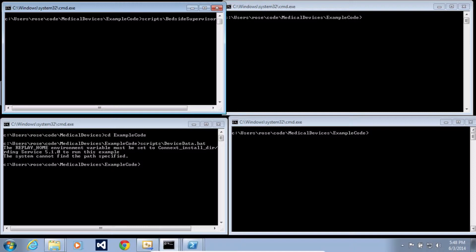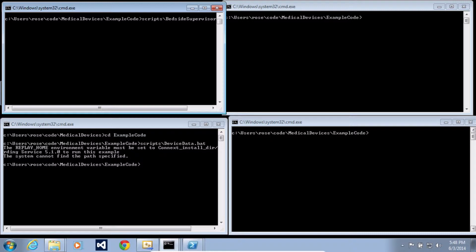The first one is the device patient mapping application. This sends out information about which device is monitoring which patient. The second application is actually an application that sends pre-recorded device data. This pre-recorded data was taken from the MDPNP, that's the medical device plug-and-play project, which is located at mdpnp.org.